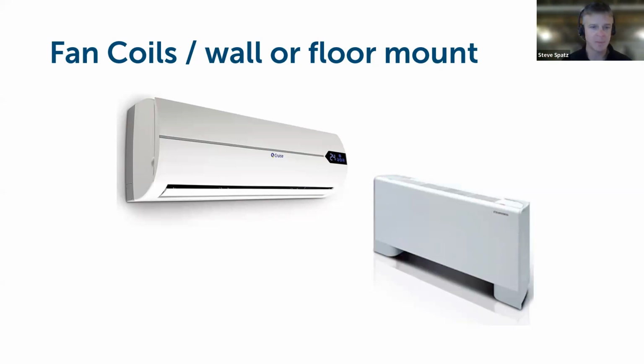You can also integrate these types of units in the home to do the cooling side, because what's happening here is you have the refrigerant pipe or the water piping moving, coiled through this wall mounted unit or floor mounted unit. And there's a fan coil in there as well. So what that means is that on the cooling side of the equation, the summer months, that outdoor heat pump unit, the refrigerant process is actually cooling down the buffer tank or the storage tank. So you're creating cool water. The cool water is being piped through these types of emitters, and then air is being blown across that cool water in that piping and providing air conditioning to the spaces. So this is one delivery mechanism for doing cooling and heating. You could do heating with these as well.